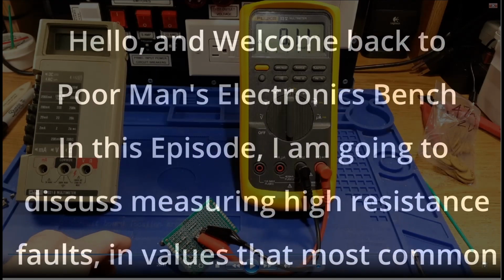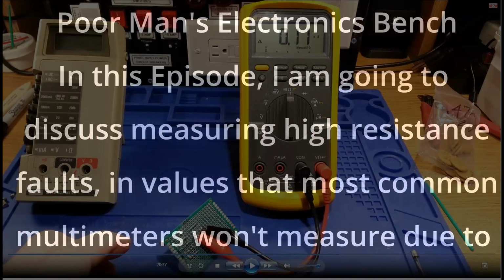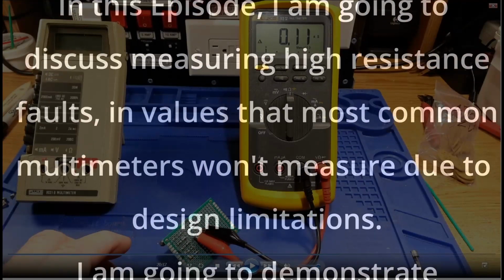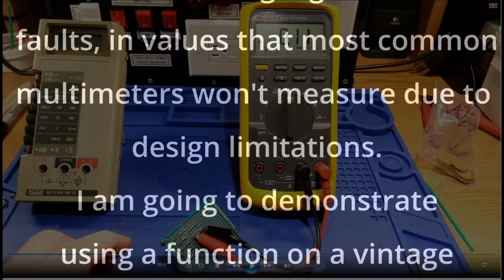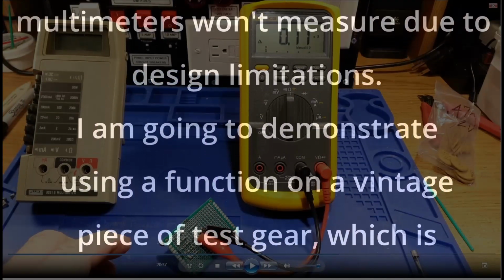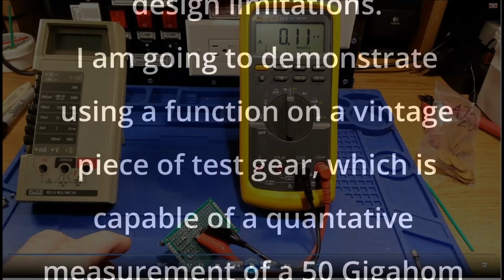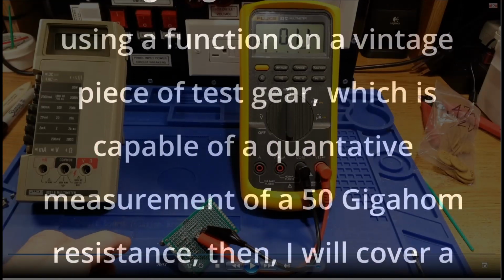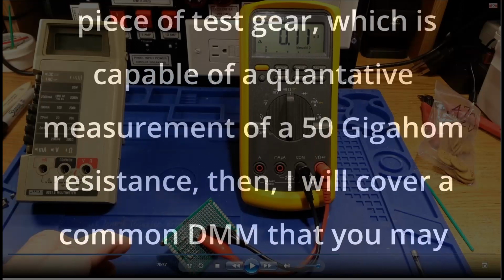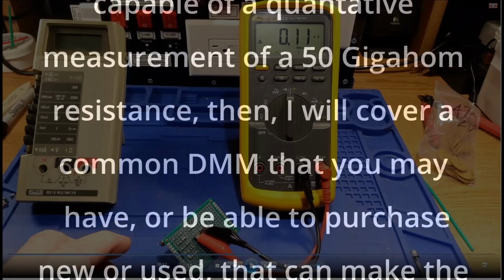In this episode I am going to discuss measuring high resistance faults in values that most common multimeters won't measure due to design limitations. I am going to demonstrate using a function on a vintage piece of test gear which is capable of a quantitative measurement of a 50 gigaohm resistance.